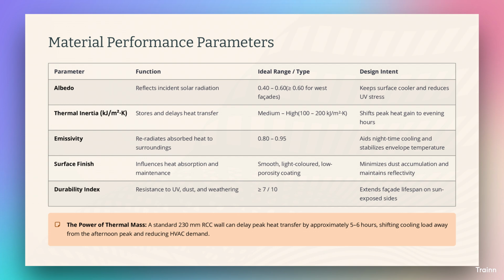Parameter: thermal inertia, kJ/m²K. Function: stores and delays heat transfer. Ideal range: medium to high, 100 to 200 kJ/m²K. Design intent: shifts peak heat gain to evening hours.